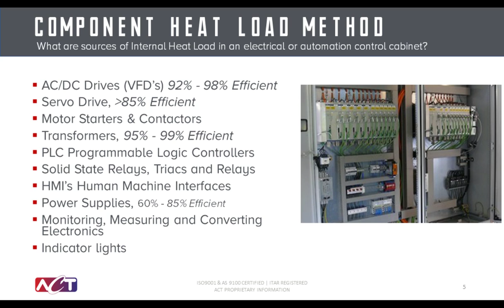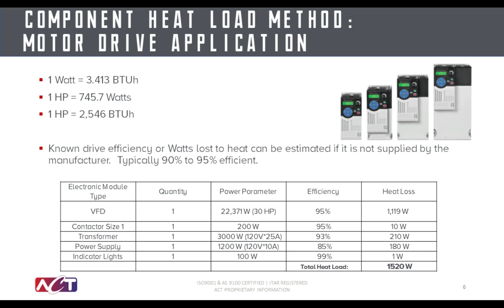For this example, this motor drive application had a few different types of electronic modules present. There are commonly found components including a VFD, a contactor size 1, transformer, power supply, and indicator lights. Now, taking each quantity, multiplying it by the power parameter in watts, by its efficiency, we calculate each respective heat loss of each component. Adding them up will give us the total internal heat load of that enclosure, which will ultimately determine what type of thermal solution will be needed.